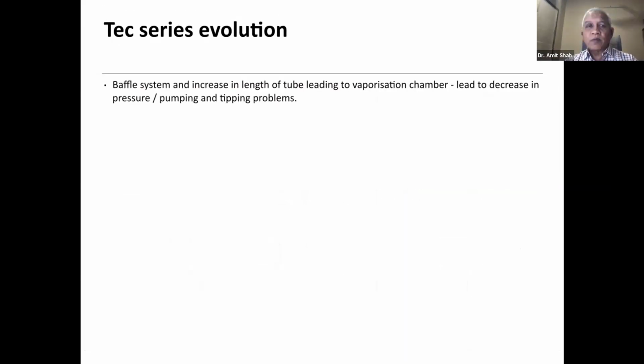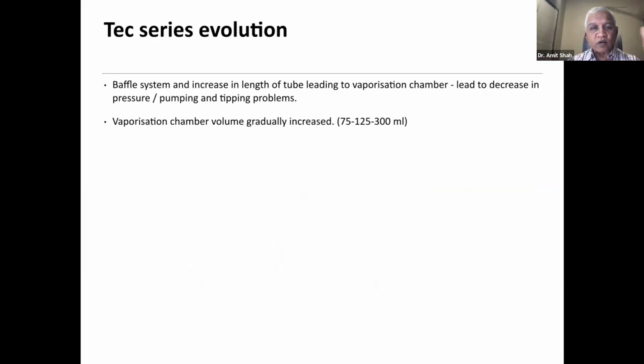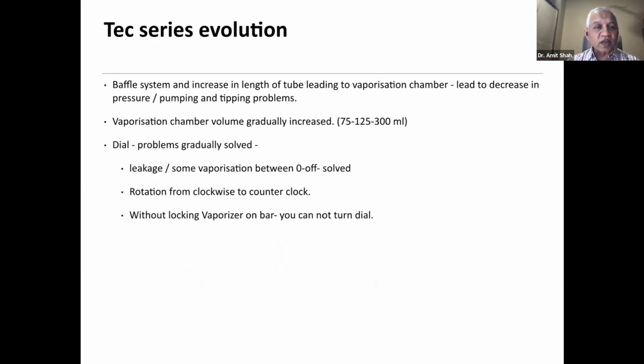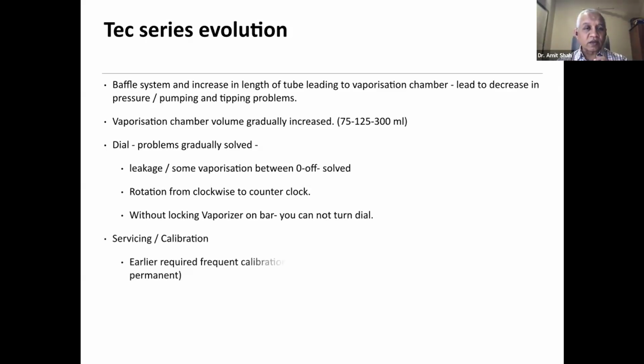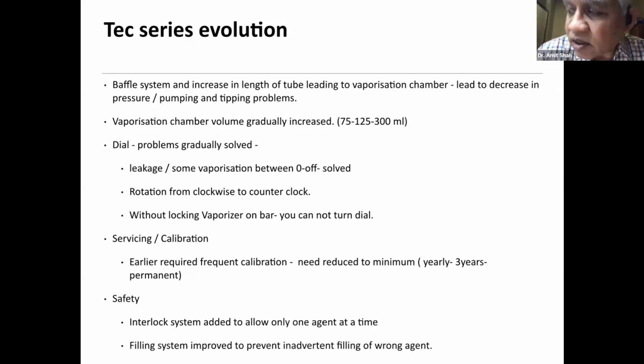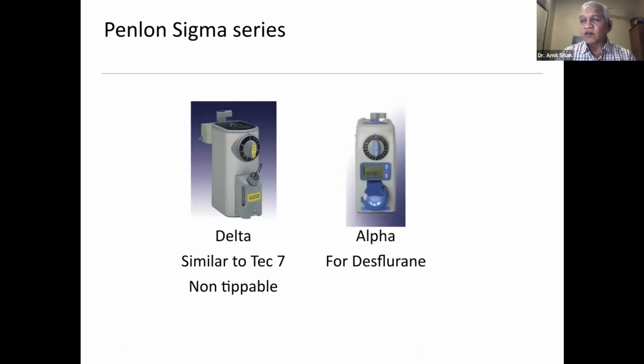So the Tec series evolution: baffle system added, increased length of the tube leading to the vaporizing chamber. So pressure, pumping and tipping problems were reduced. Vaporizing chamber volume was gradually increased from 75 to 300 ml. Dial problems were gradually solved. Rotation turned from clockwise to counterclockwise. And without locking the vaporizer on the bar, you cannot turn the dial, which I showed. So you just cannot turn the vaporizer on. You have to lock it, then only can you turn the dial. Earlier, frequent calibrations were required. Now it is permanent. You don't require calibration for Tec 7 and newer versions of the vaporizer. Interlock systems were added, and filling systems were added to prevent inadvertent filling of a wrong agent, which we'll discuss after 2-3 slides.